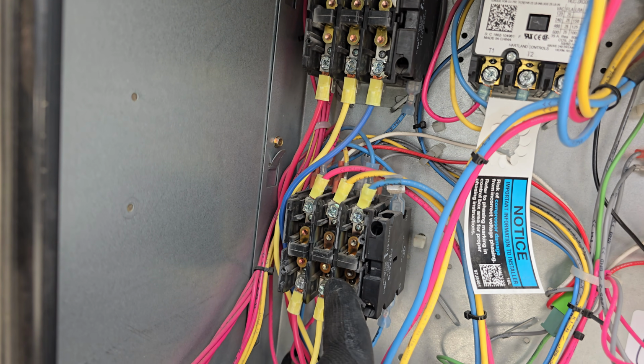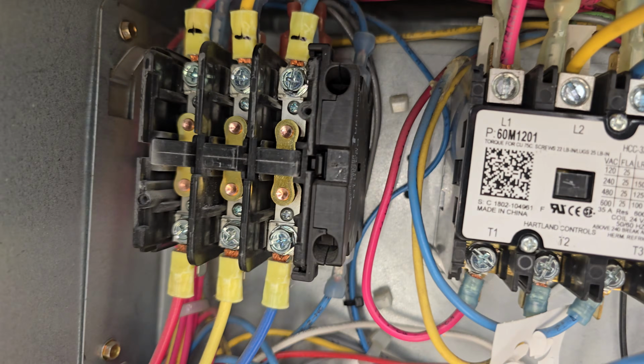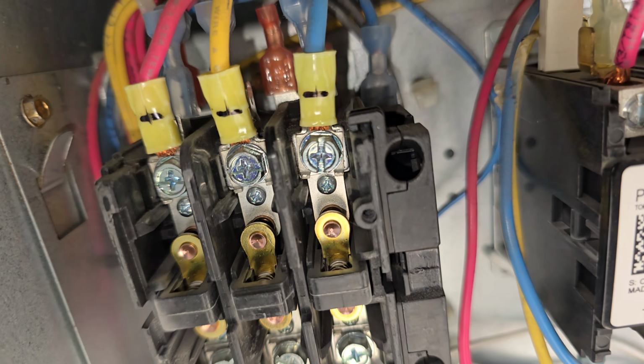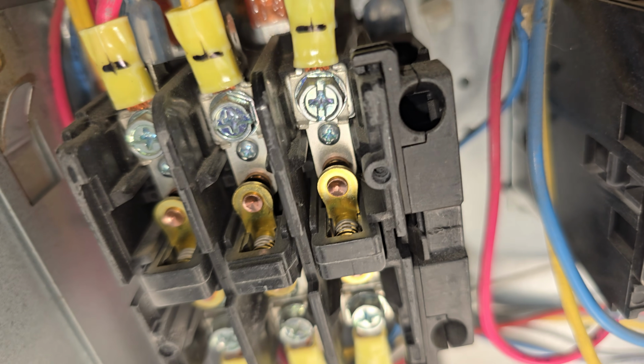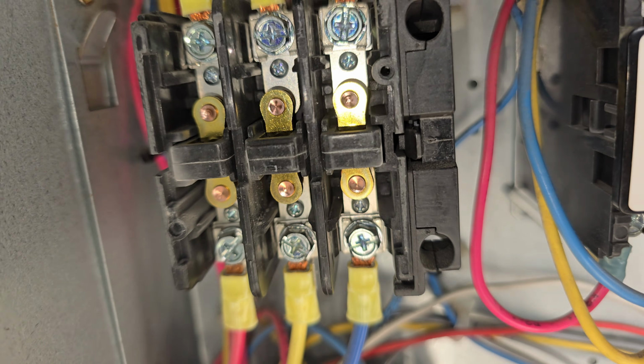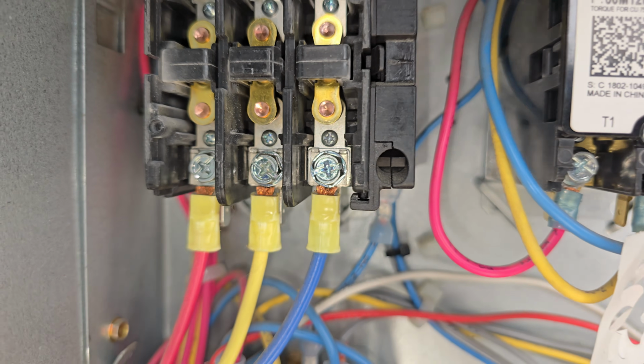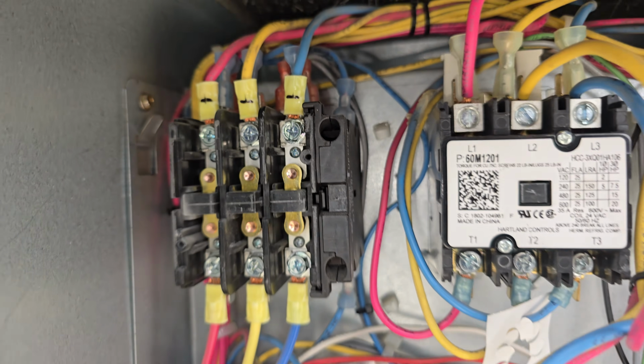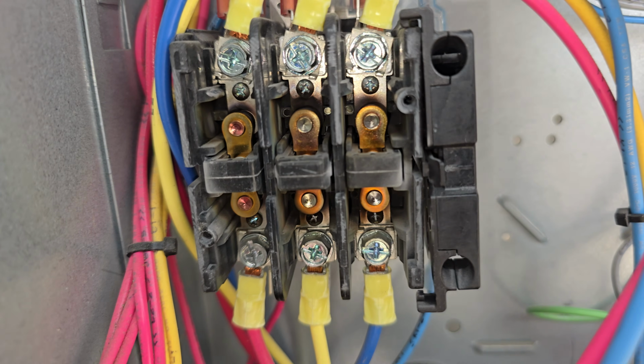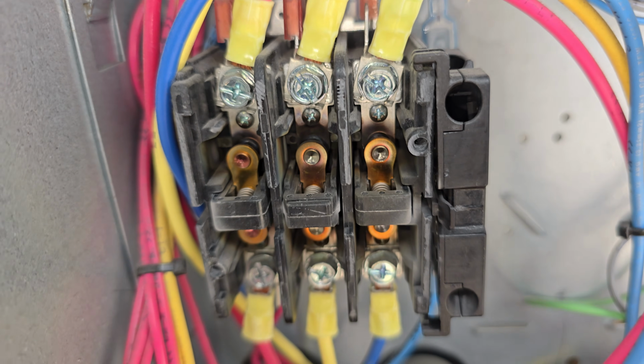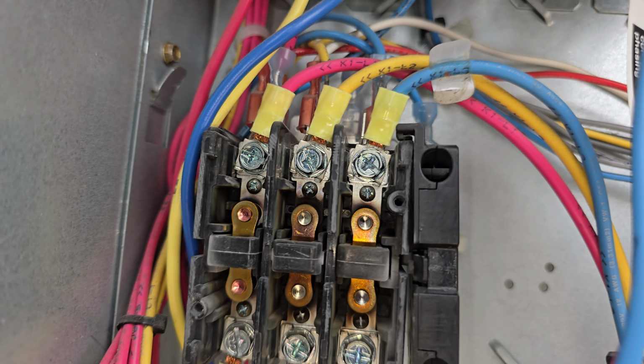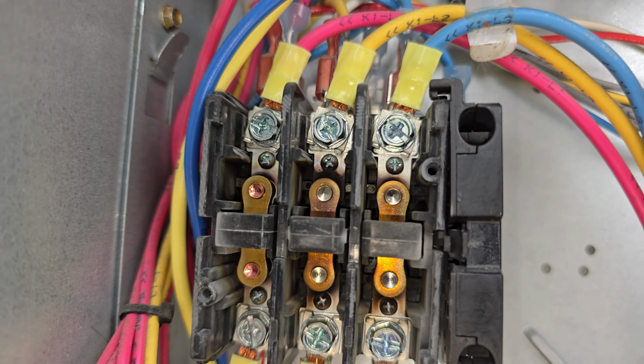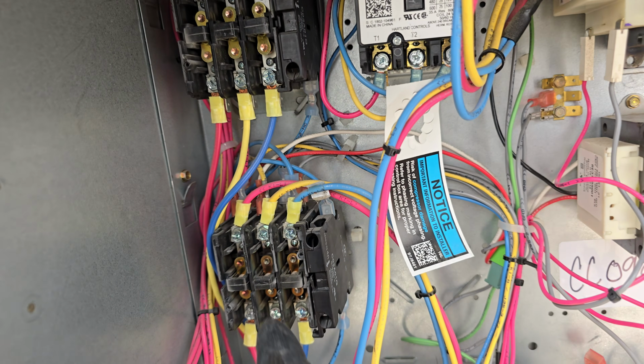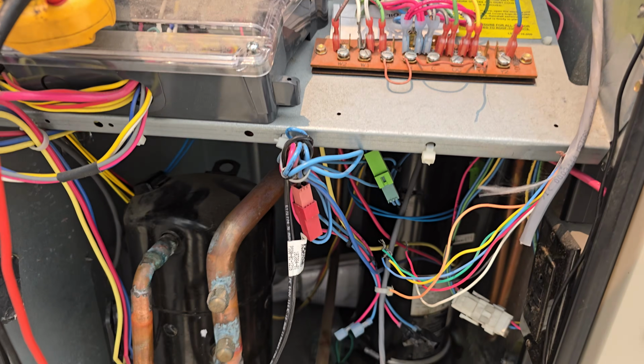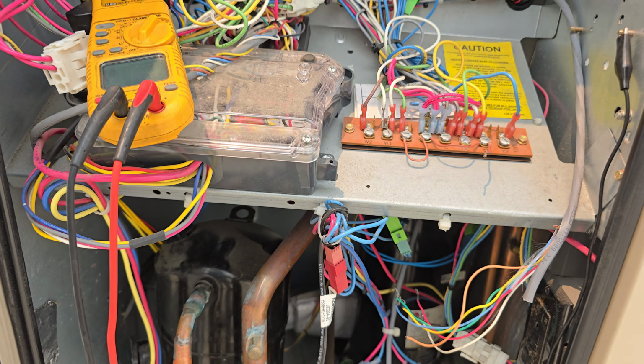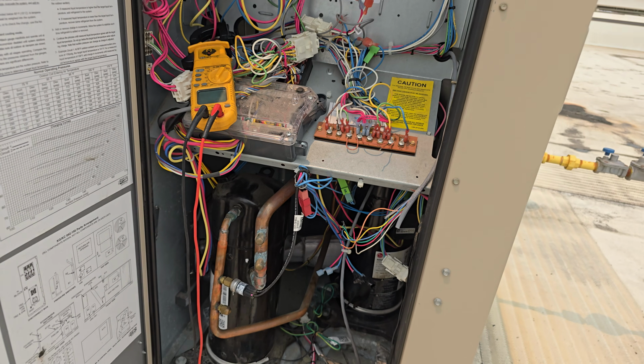So this second contactor, looking at it, is really clean. I don't see any problem, even though the compressor didn't come on here. This is the compressor to that contactor, to that one. But look at the second contactor, really burnt out. So my next step now is to eliminate compressor number 2, and I want to bring this one on and see if it holds.